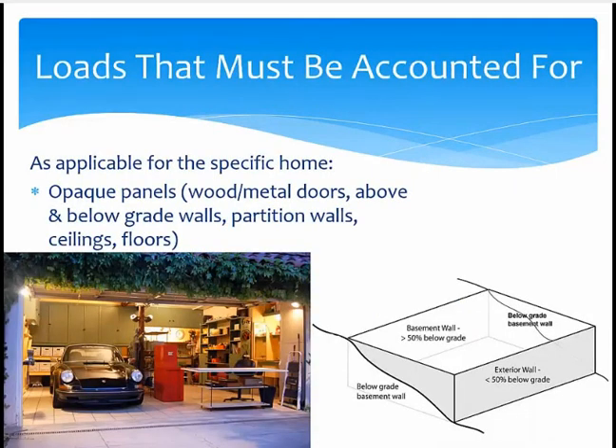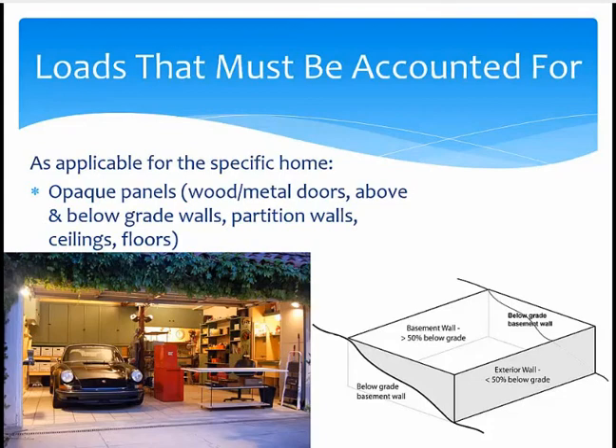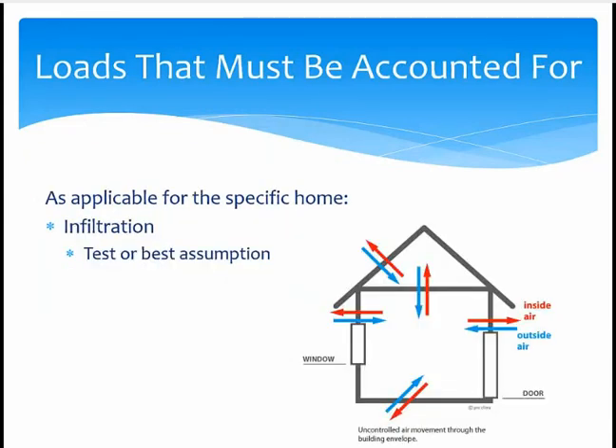The next set of loads a designer has to account for are the opaque panels. These include the wood and metal doors, above and below grade walls — that is, above and below ground walls — which are the exterior walls. There are also partition walls, which are interior walls, and there are ceilings and floors. The designer needs to account for each one of these. Infiltration is the next load that has to be accounted for — the uncontrolled air leakage into the conditioned space through cracks, openings, and leakage through the attic, ceiling, crawl spaces, and/or the basement if applicable.